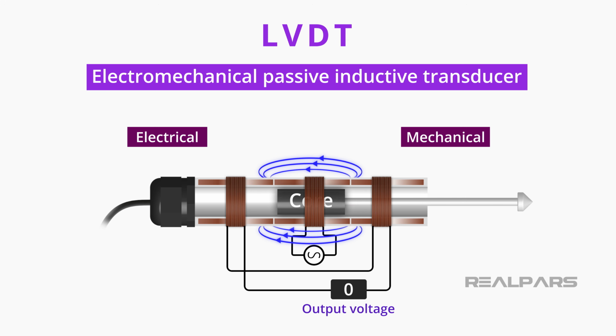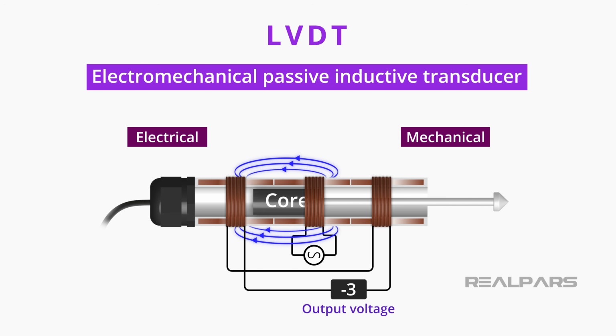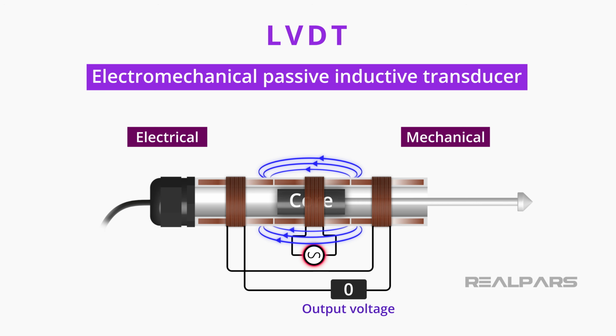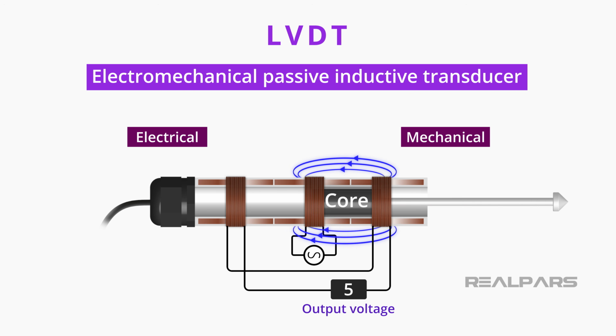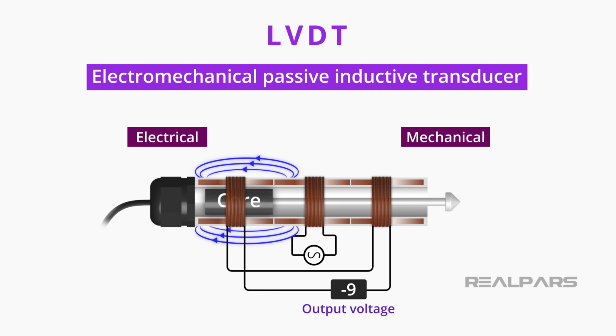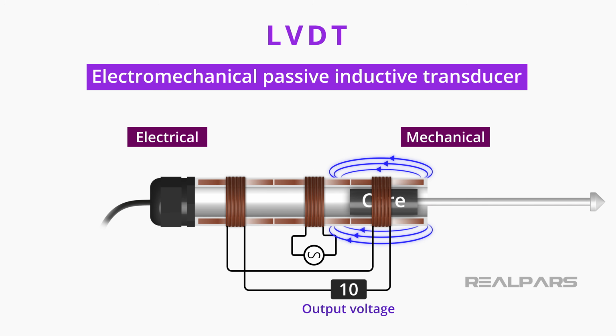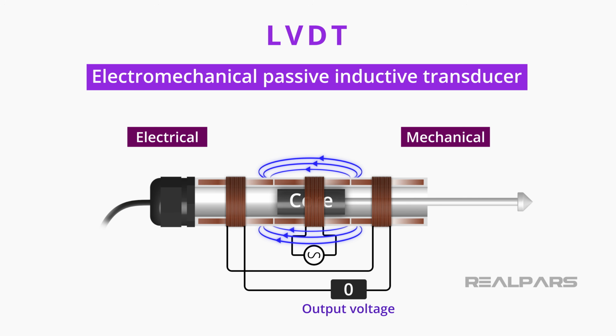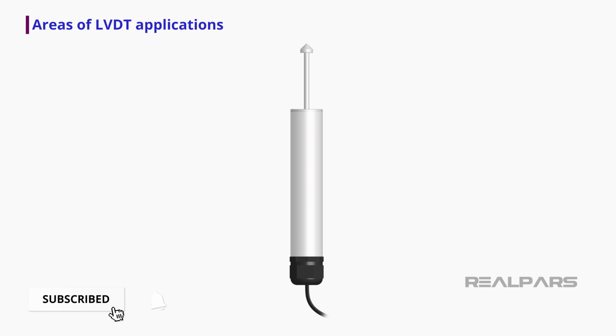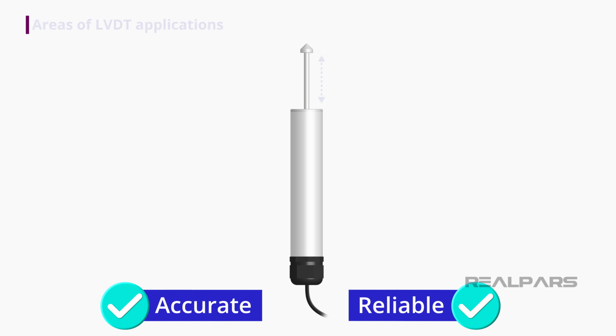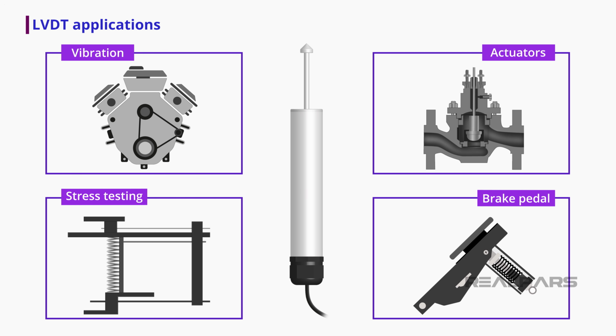We now know that our LVDT is an electronic device that has both electrical and mechanical processes. It requires an external power source to be able to operate. It stores electromagnetic energy and converts some form of energy into a readable signal to describe the movement of a body along a sole axis, or what we call linear displacement. An LVDT sensor is one of the most accurate and reliable methods for determining linear distances. They are commonly used in a very wide range of applications across numerous industries. They can be used to detect vibration, for stress testing, to measure great displacements such as actuator movement, brake pedal travel, among much else.